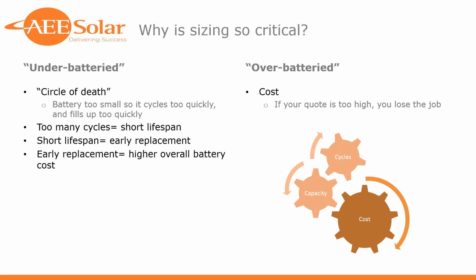The system runs but does not perform well. Essentially, what's going to happen in most of these cases is the battery's just going to cycle too much. The battery is too small, so it's going to discharge more quickly than optimal. You're going to discharge it, charge it, discharge it, charge it, and that's going to lead to early replacement. That's kind of a rosy picture for a worst case scenario. I think the true worst case scenario is in not lining up your battery with your charge amps. You're going to kill the batteries very quickly, or possibly cause some bodily harm or some mechanical equipment failure.